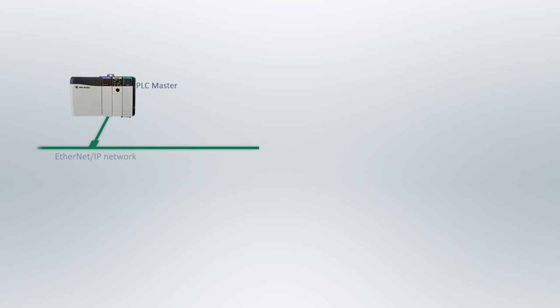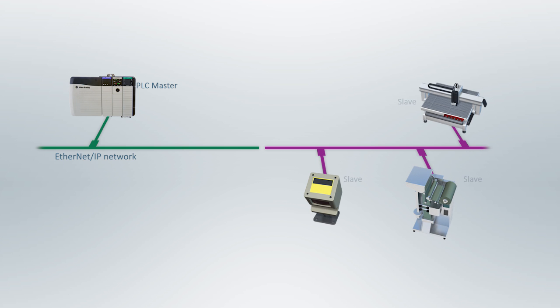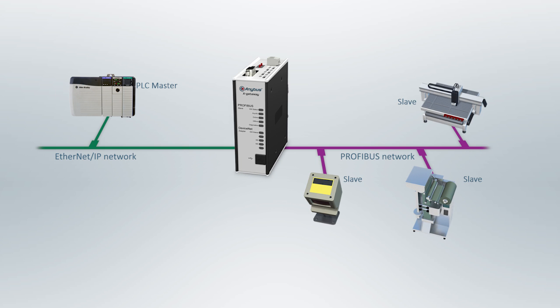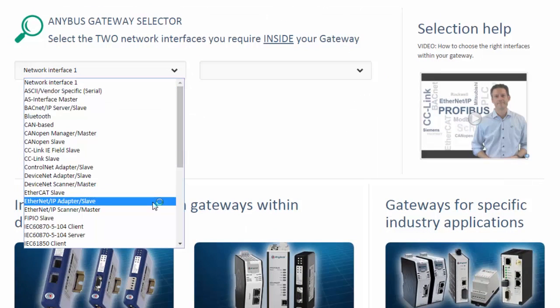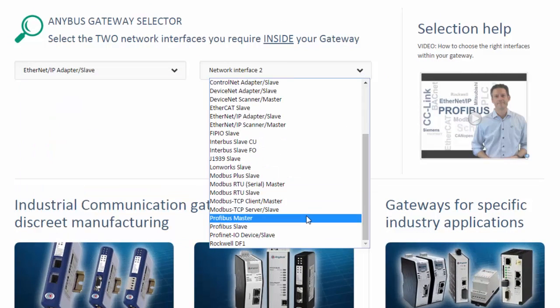Confusing? Well, let's have a look at some examples to explain this further. In our first example, we have an Allen Bradley ControlLogix PLC which uses an Ethernet IP network. We want to use a gateway to integrate Profibus automation devices into the ControlLogix PLC. Consequently, the gateway is a slave on the Ethernet IP network. Since there is no controlling PLC master for the Profibus devices, the Anybus gateway acts as a master in this case, saving you the cost of an additional master. So the solution here is an Anibus X gateway which is an Ethernet IP slave and a Profibus master.